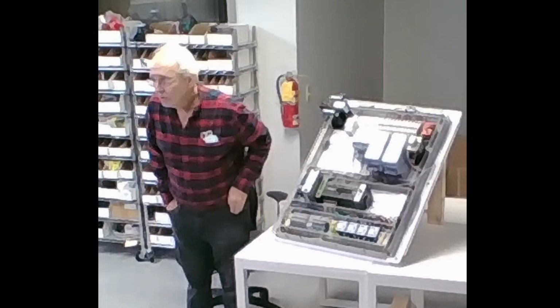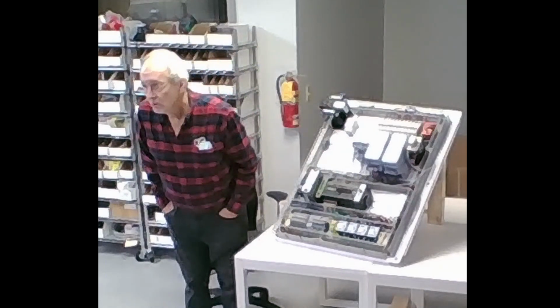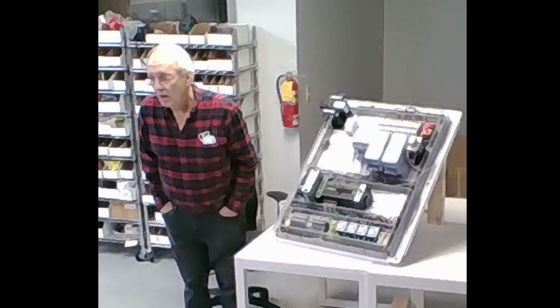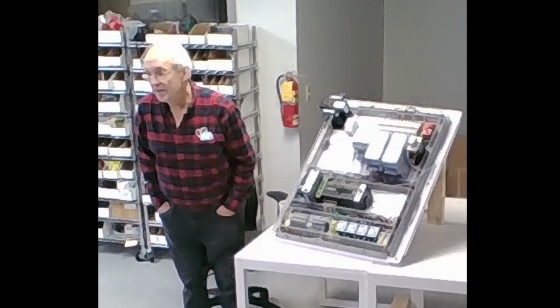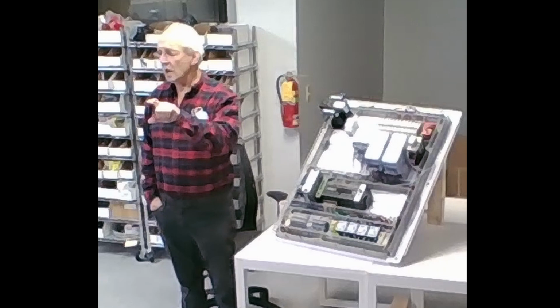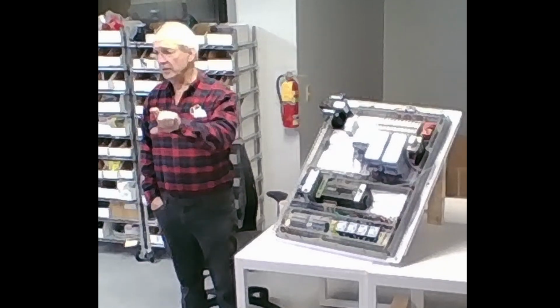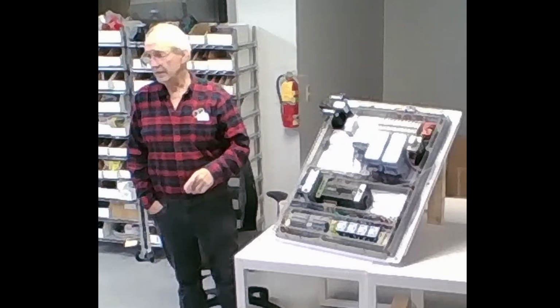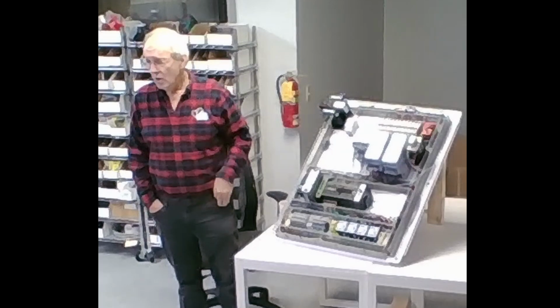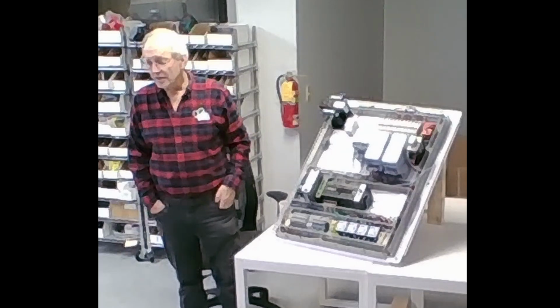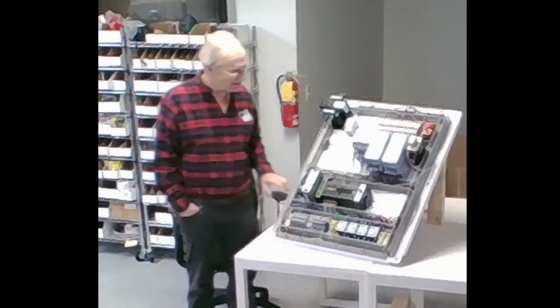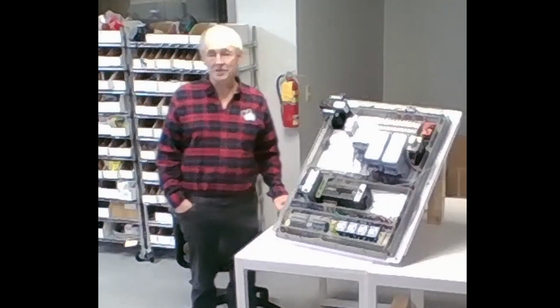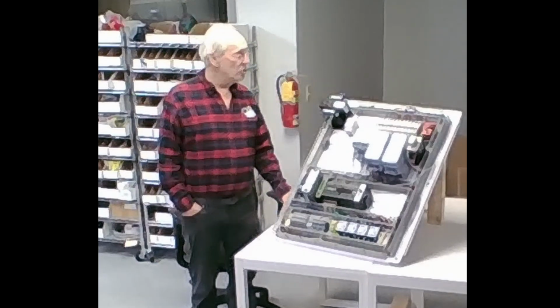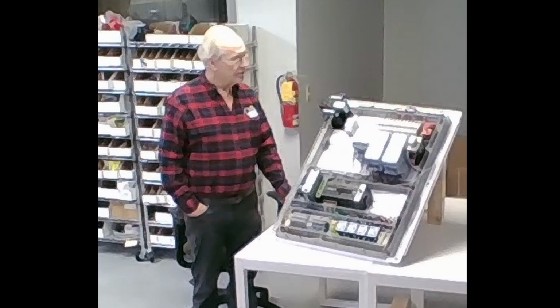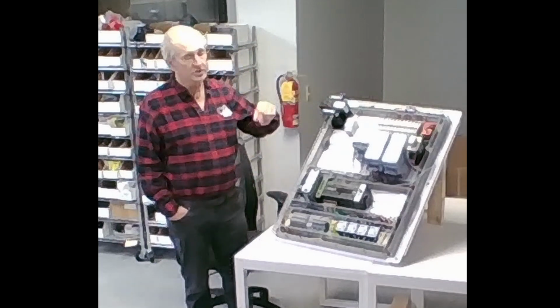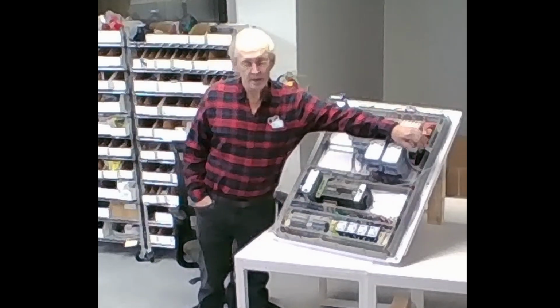Sorry, quick clarification. So a contactor is similar to a relay, it just has less arcing. Contactors are always double break, where relays are only single. So a contactor is a relay, but a relay is not necessarily a contactor. Correct. Yes, that's exactly right. Okay, so they function the same way. All right. So that's how we interlock the safety circuits through the main contactor.